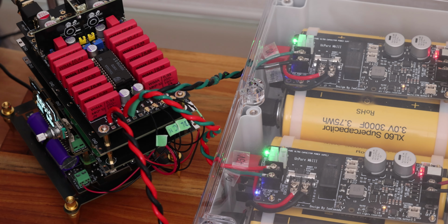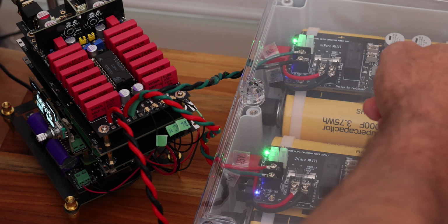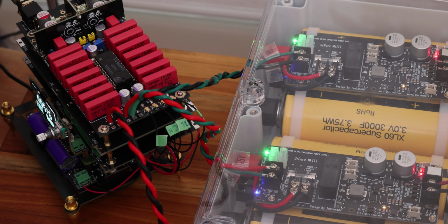I put together a list of some of the safety things that you could use to improve your setup. I'm just going to go through them. This is only a partial list, and it's not going to make you safe, but like I said, every layer counts and it makes you slightly safer. Number one is to have fuses on each low voltage line, so the low voltage lines that are going into the UC should have fuses on them. You should also have a fuse on the main transformers as well.